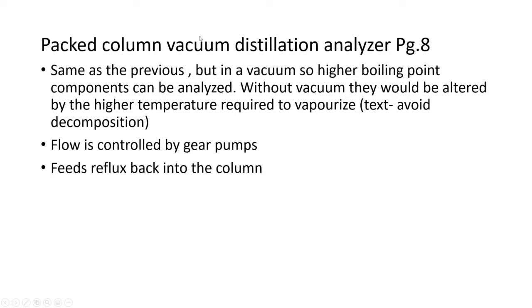The last analyzer in distillation is the Packed Column Vacuum Distillation Analyzer — essentially the same as the previous ones except it uses a vacuum so we can boil higher-boiling-point components at a lower temperature. Without the vacuum, they would decompose or burn at the higher temperature required to vaporize them. The main difference from the IBP/FBP analyzers is that this system has flow controlled by gear pumps rather than pressure and orifices, and it feeds reflux back into the column.